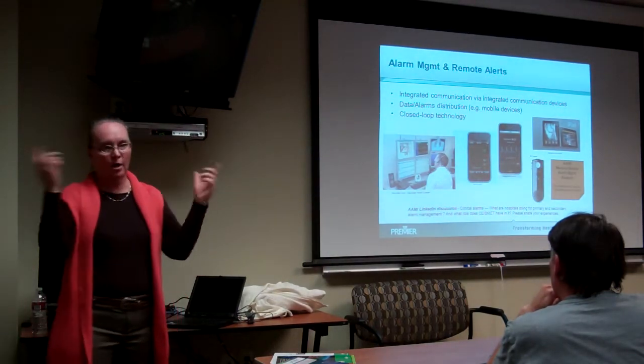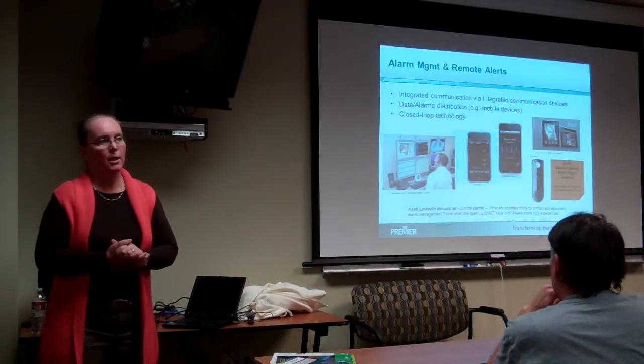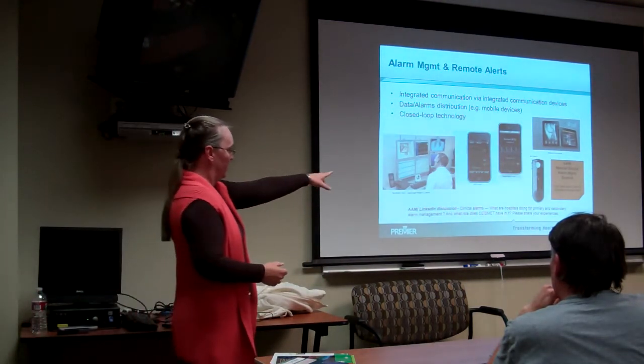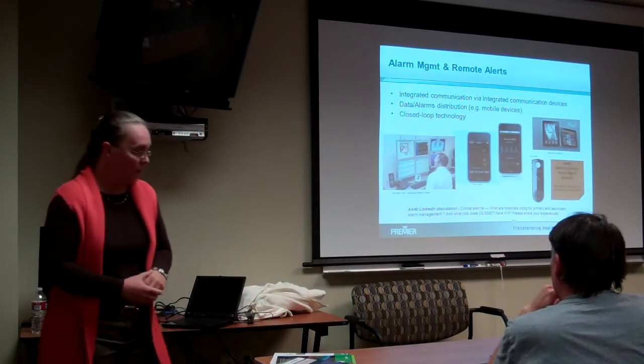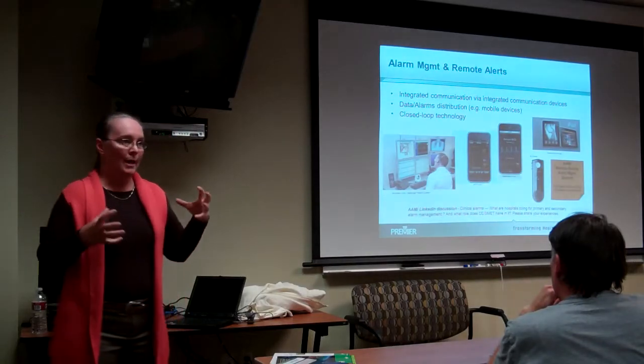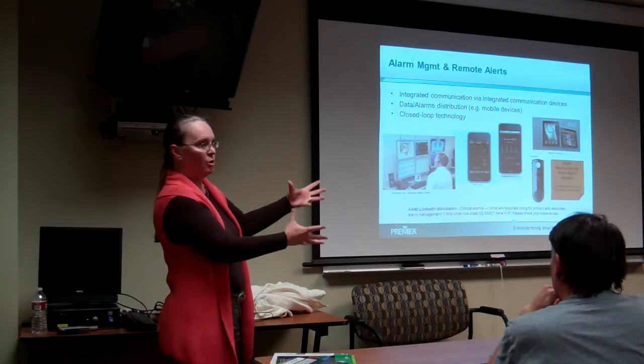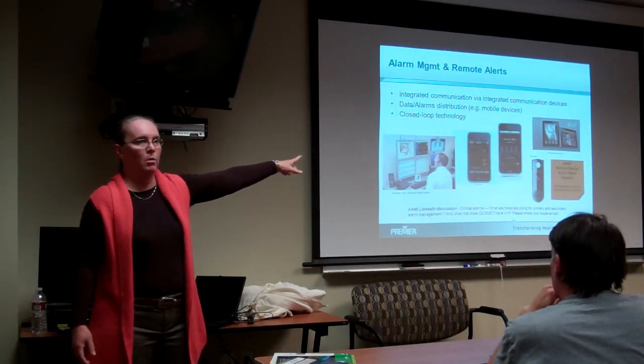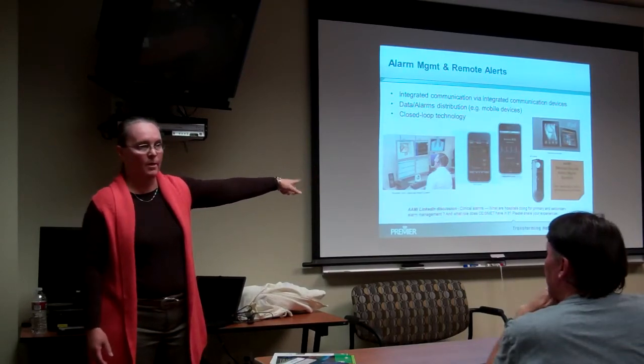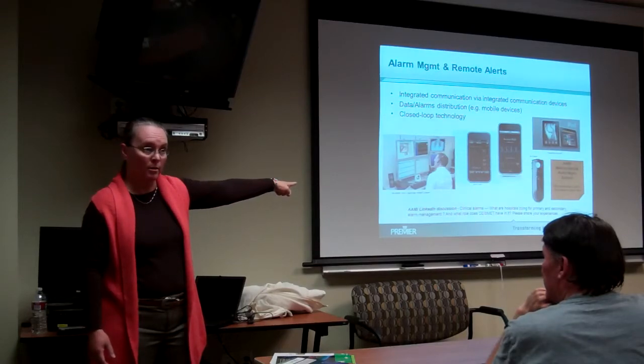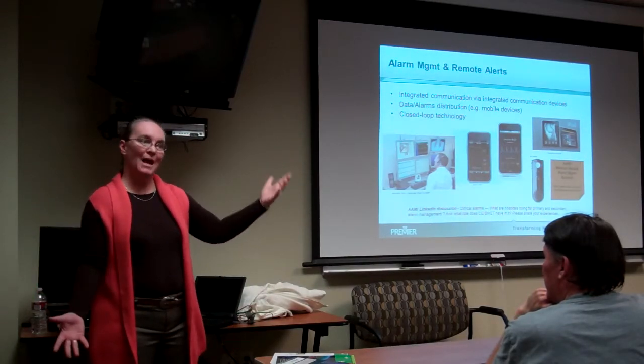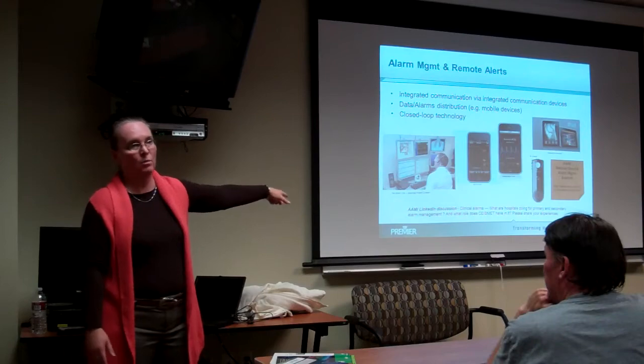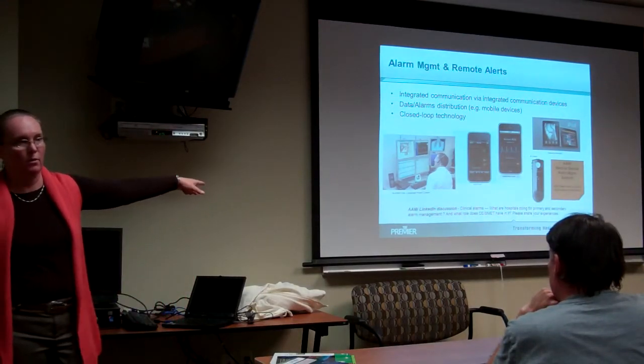There are pagers, cell phones, and a zillion different tools — toys, I like to call them — out there. But keep in mind, and this came up significantly at the Medical Device Alarm Management Summit held in early October: you have your primary alarm, our traditional bedside and central station monitors, and then all these other things are secondary alarms. But many hospitals that are deploying these tools are using them as their primary. So how do you manage that both technically and from a risk management and patient safety perspective? What happens if that communication network goes down? What is your fail-safe?